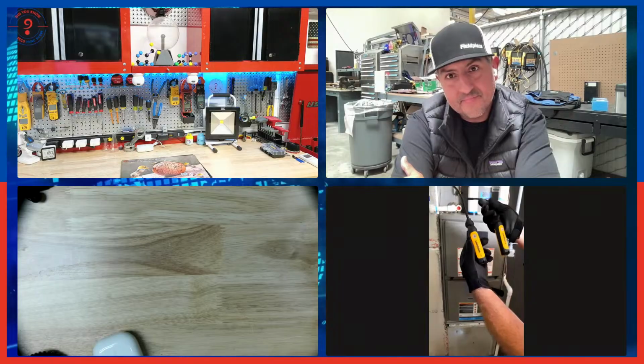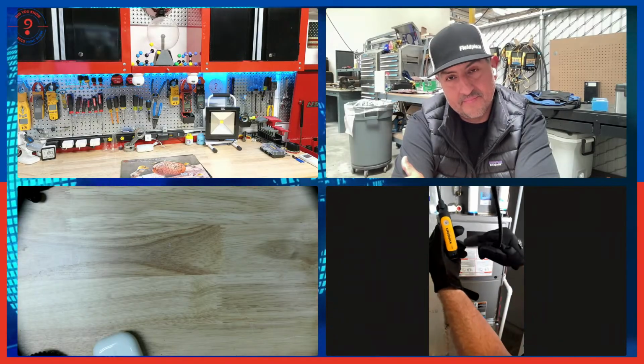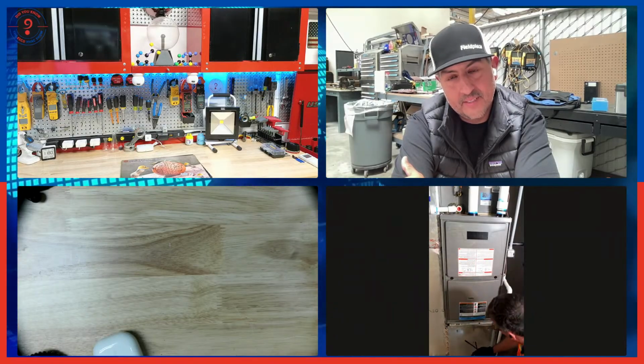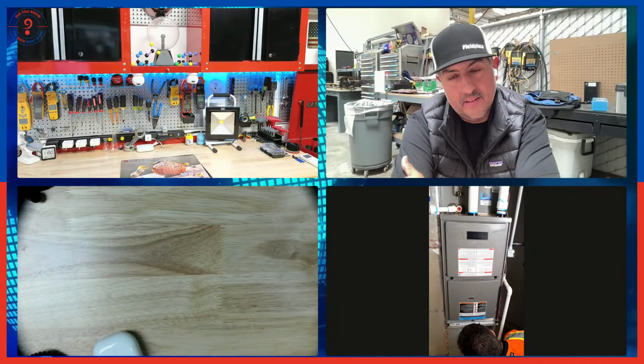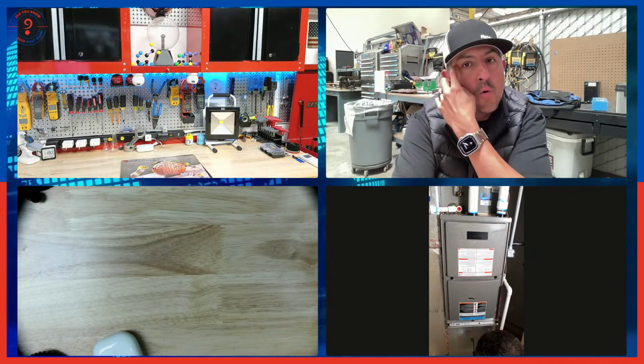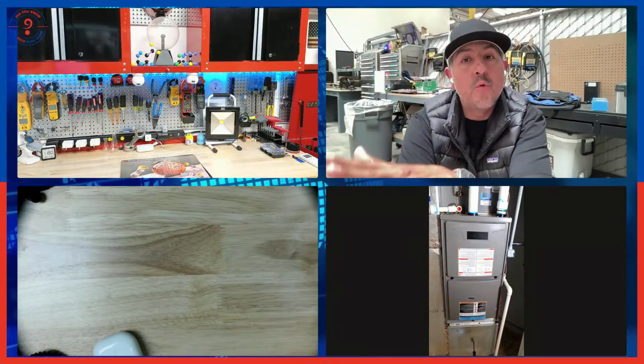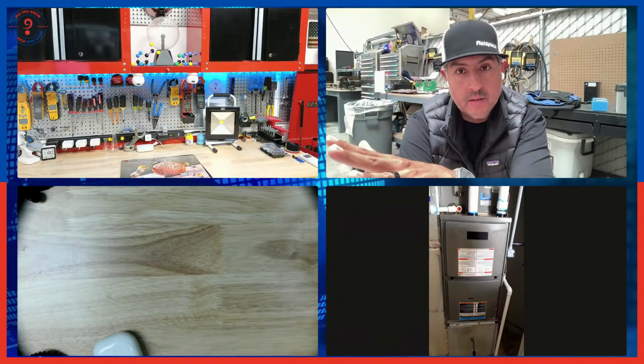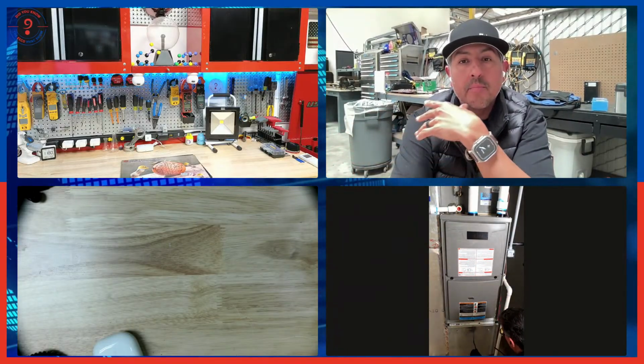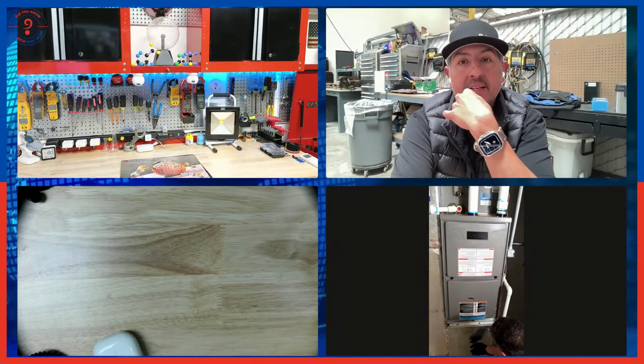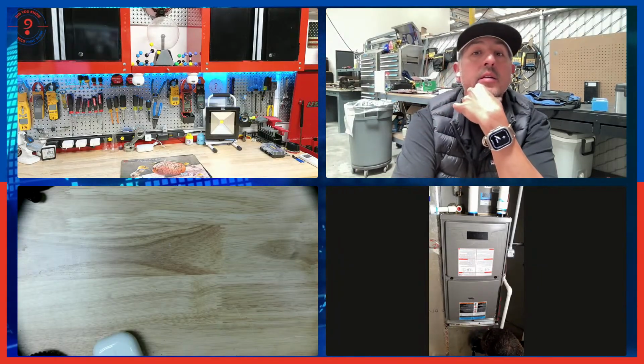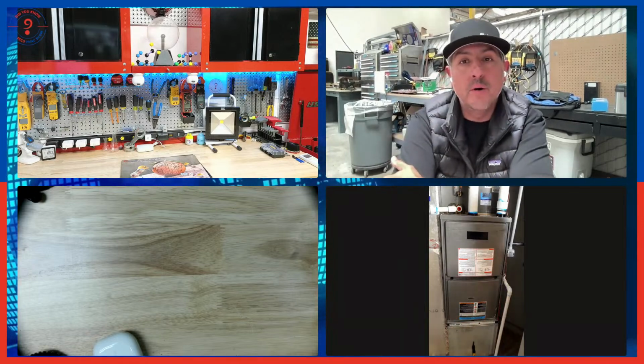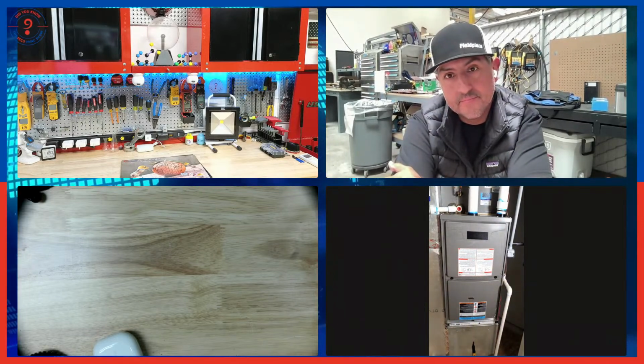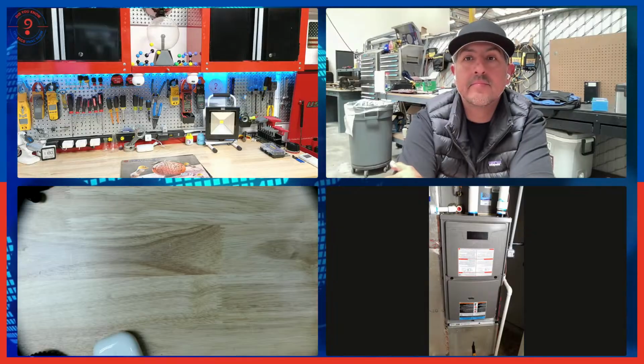We're going to verify, because remember, our probes are color coded. I'll use blue for my low, or return side—wait, return side would be red. Yep, return would be red. The idea is that the return side is hotter than the supply side in cooling mode. Makes sense. All right, and I went ahead and used my magnet on that.